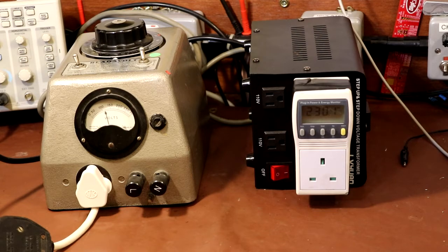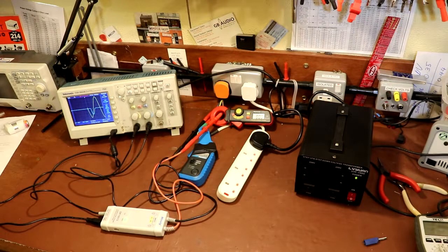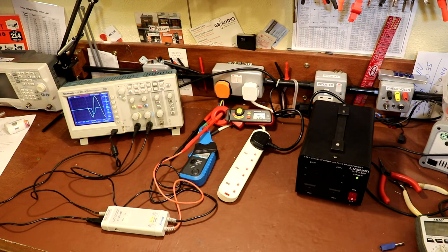If you look at the Amazon listing for this transformer, it describes it as being a low inrush transformer. Now for a conventionally wound transformer, the inrush current can be as much as 10 times the full load current, and for a toroid it can be as much as 60 times the full load current.